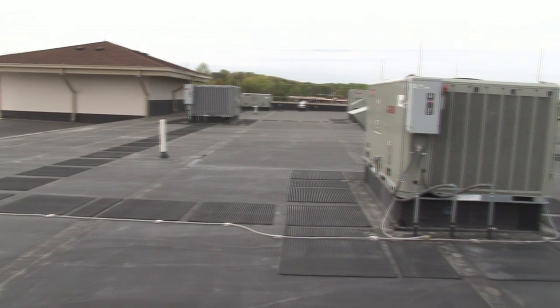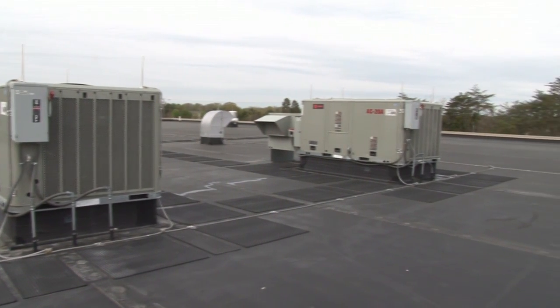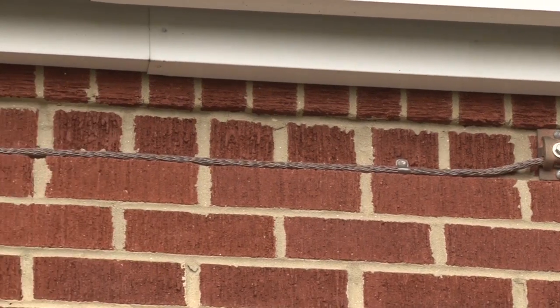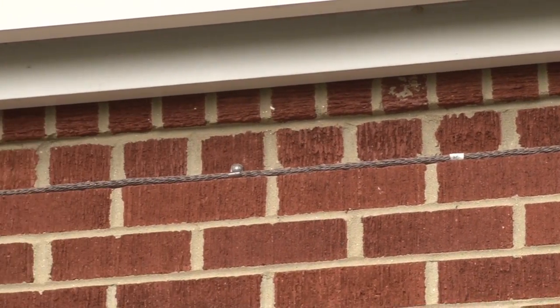What's important at roof level, especially on a flat roof, is interconnection of metal bodies to the lightning protection system. You don't want what's known as a side flash occurring between the grounded lightning protection system and an ungrounded metal body. So consequently, metal bodies — air conditioning units, exhaust fans, vent pipes, railings — we interconnect those to the lightning protection system.